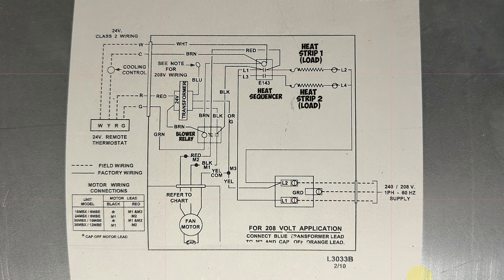So let's go ahead and trace out L1. This is 120 volt right here. And L2 is also 120 volt. And combined, they are 240 or 208 volt. L1 is going to be the bold black. So it goes up to L1 and L3 of the heat sequencer terminals, which are normally open because we need these to close for it to make it to the heater. But right now they're open. And we have this wire right here piggybacked off the terminal of the heat sequencer. And let's look where this goes. This goes to the fan relay, the normally open side of it.